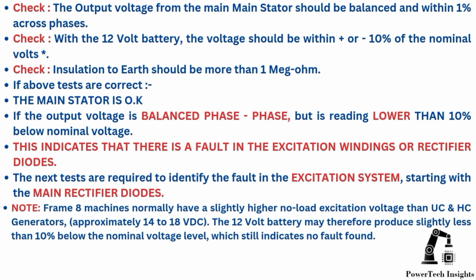Check. The output voltage from the main stator should be balanced and within 1% across phases. Check. With the 12-volt battery, the voltage should be within plus or minus 10% of the nominal volts. Check. Insulation to earth should be more than 1 megohm. If the above tests are correct, the main stator is OK.